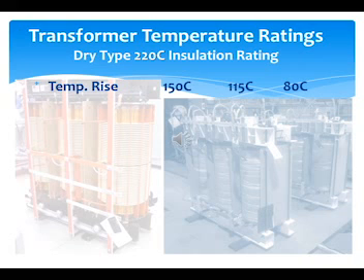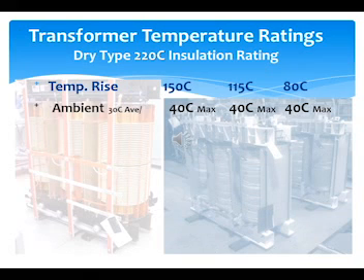Regarding temperature rise, there are three ratings included in the standard: 150C, 115C, and 80C. The rated temperature will potentially be achieved when the load reaches full KVA. For example, for a 1000 KVA transformer, 150C is added when the load reaches 1000 KVA.